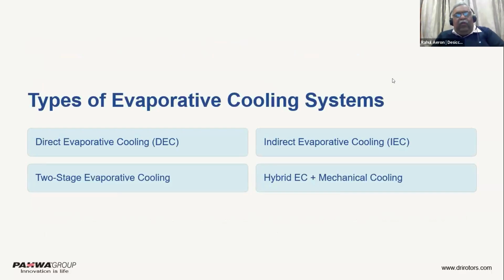Coming to the basics of evaporative cooling, as I mentioned earlier, the direct evaporative cooling system is something we have been using. Basically, there is a pad on which water is sprayed, and there is a fan. Because of the evaporation of water, the air is cooled and some amount of moisture is added to the air. That is called a direct evaporative cooling system.